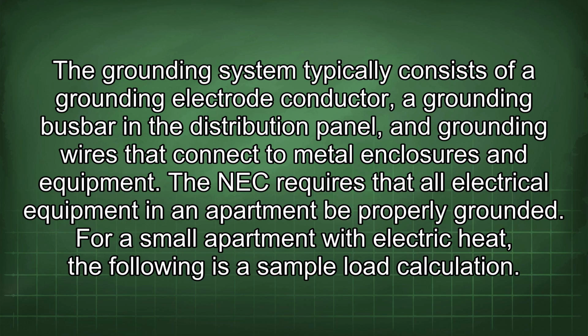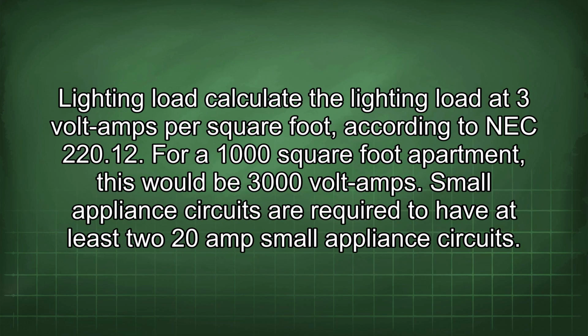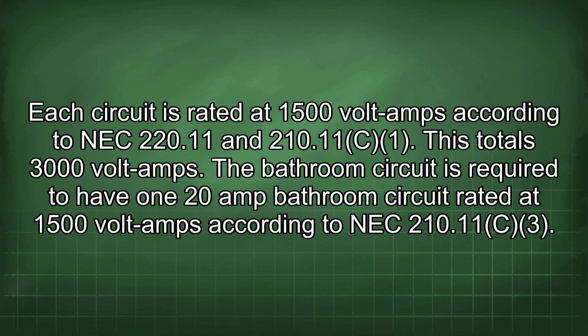For a small apartment with electric heat, the following is a sample load calculation. Lighting load: calculate the lighting load at 3 volt-amps per square foot, according to NEC 220.12. For a 1000 square foot apartment, this would be 3000 volt-amps. Small appliance circuits: at least two 20 amp small appliance circuits are required. Each circuit is rated at 1500 volt-amps according to NEC 220.52 and 210.11. This totals 3000 volt-amps.